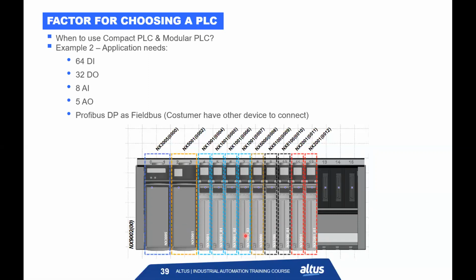1001. Here digital inputs 16, 32, 48, 64. And here NX 2001, 32 digital outputs, 16 plus 16. And here NX 6000, 8 analog inputs, just one module. And here NX 6100, two modules, because each 6100 supports 4 analog outputs. So we have 8 analog outputs available here.